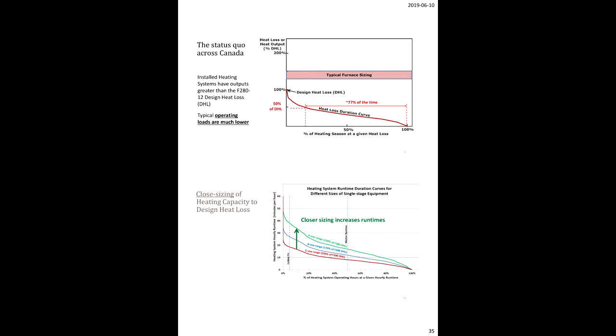Traditionally, our answer is to put in more ductwork. That's not going to solve it. The reason the moisture levels were going up and the basements turned into swamps was because the air conditioning was short-cycling. Come on, turn it off — an air conditioner doesn't start removing moisture until it's run for 8.5 minutes.